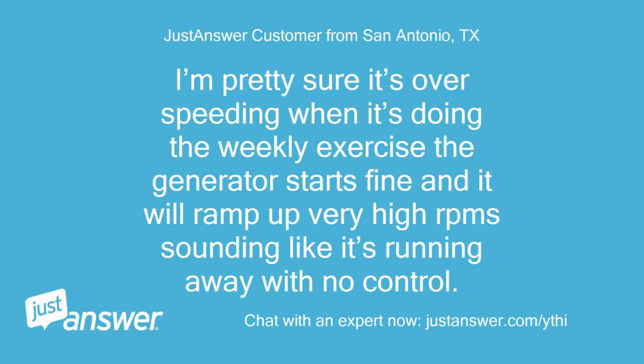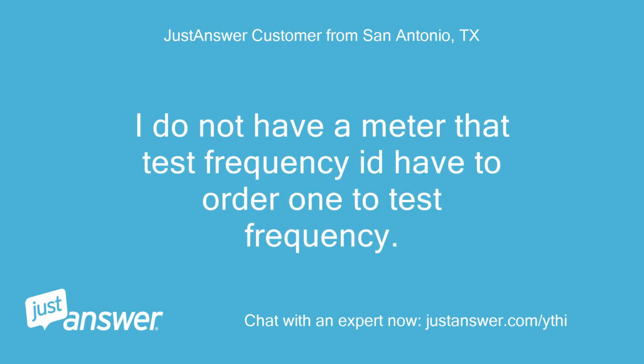I'm pretty sure it's overspeeding. When it's doing the weekly exercise, the generator starts fine and it will ramp up to very high RPMs, sounding like it's running away with no control. I do not have a meter that tests frequency. I have to order one to test frequency.